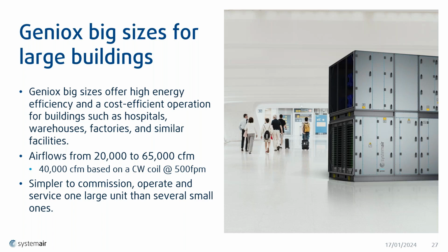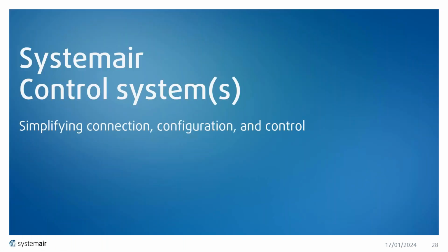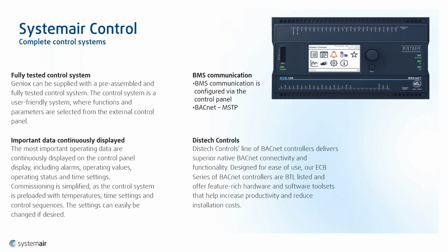Once you start doing that, based on the actual available size that you have within the unit, your CFM for a chilled water coil will drop down to about 40,000 CFM. So if you're going to be just having a heating unit or a filter unit, 65,000 CFM or a recovery unit is not a problem. But if you've got a chilled water coil in there, you are going to be dropping down based on 500 feet per minute. Again, these can be tweaked and changed if you're wanting to go a little bit higher than that. But based on good engineering practices, we always say that it's not good to go too high on the actual face velocity.